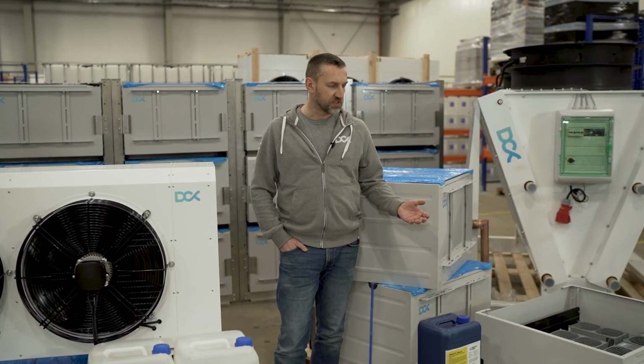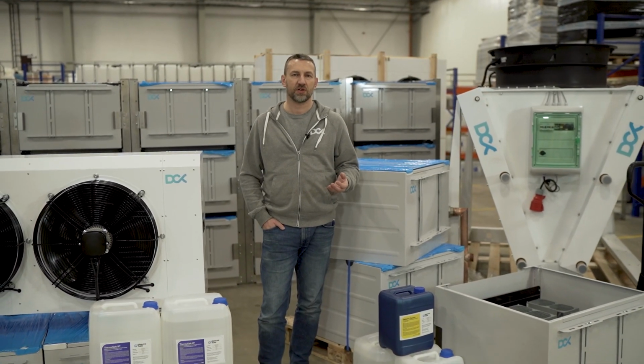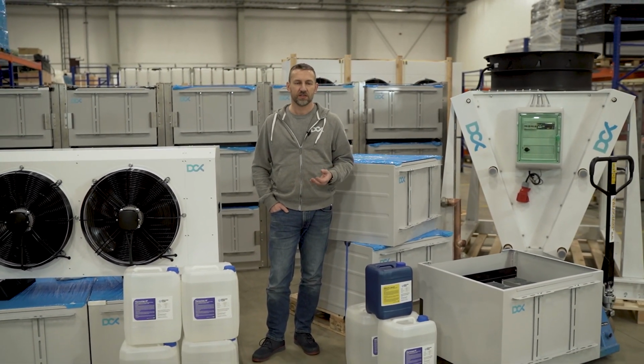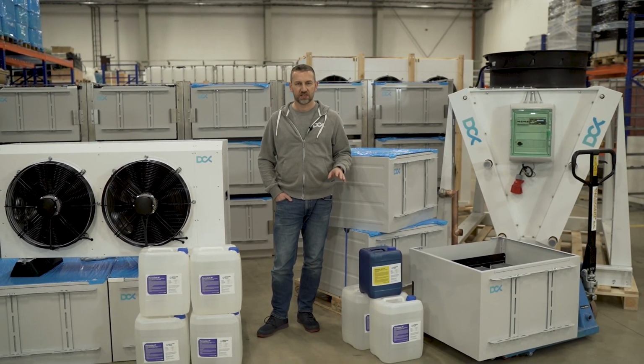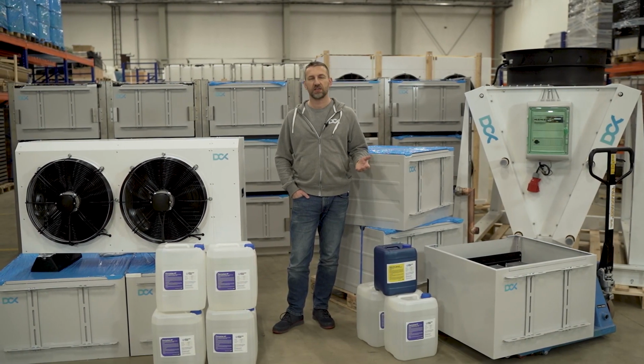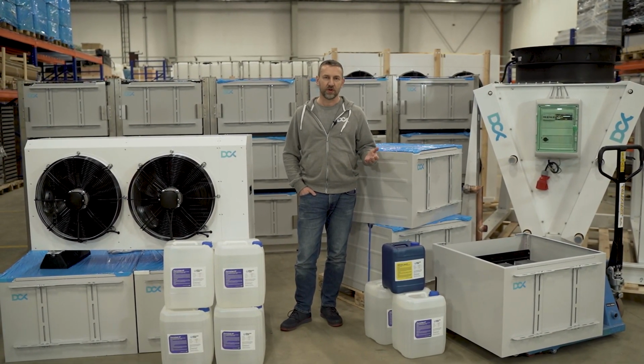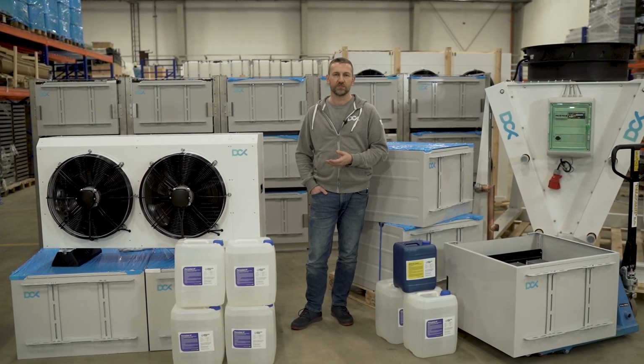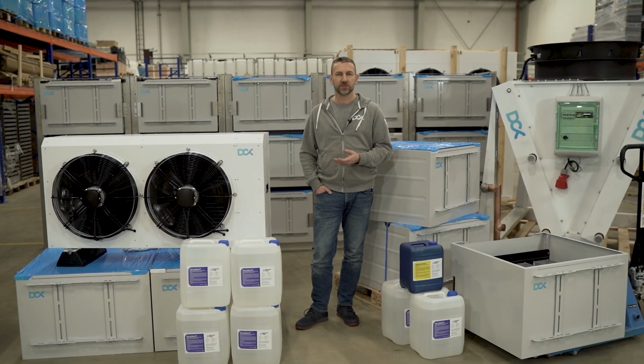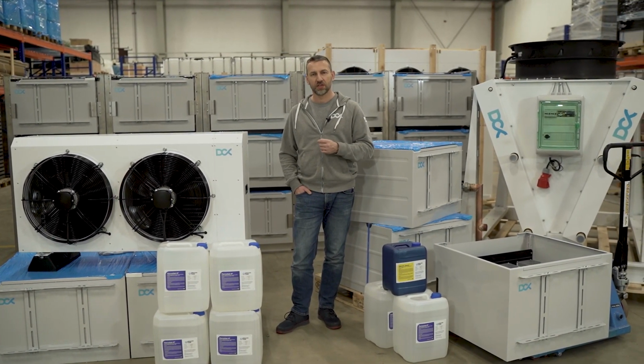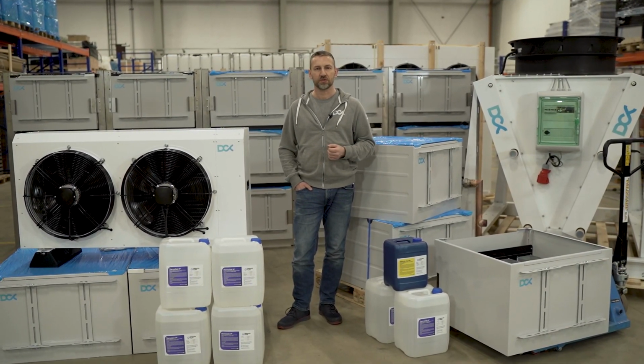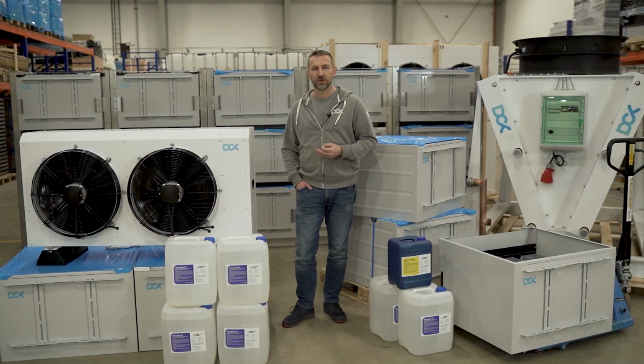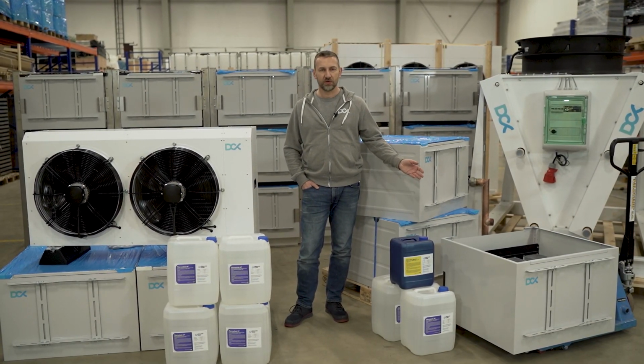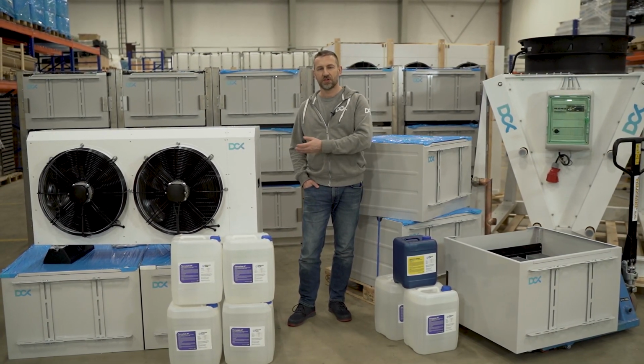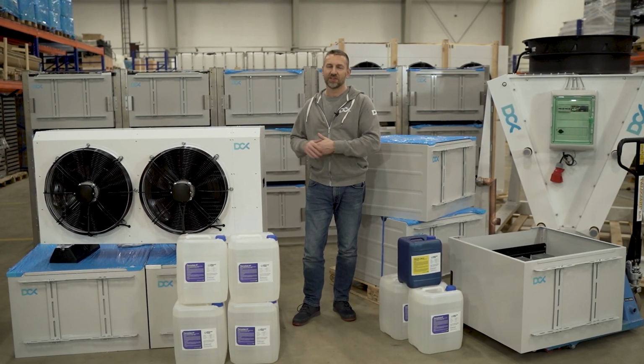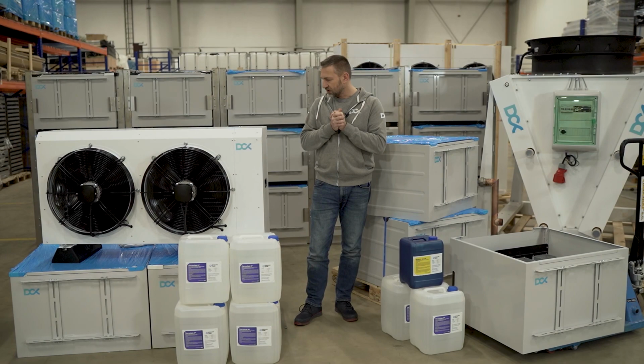Inside the system, the only thing that works is a pump running at about 40 decibels, so your operation is almost silent. We are removing all the fans — for the S19, for example, we remove 4 fans from the miner plus 3 fans from the power supply, saving over 1 kilowatt of power those fans normally use. So there are additional power savings in the long run, counting the kilowatts used by fans and by air management in your location.